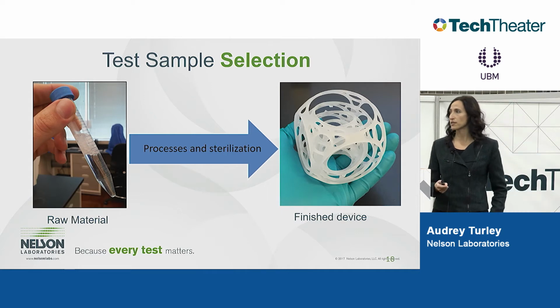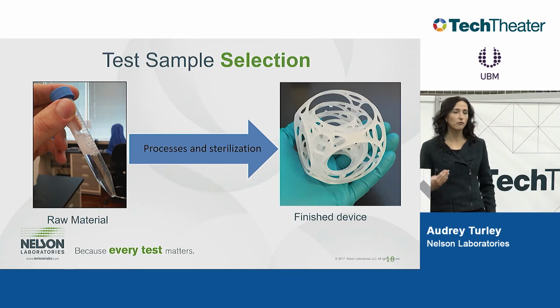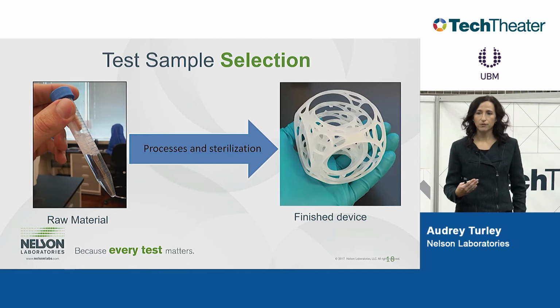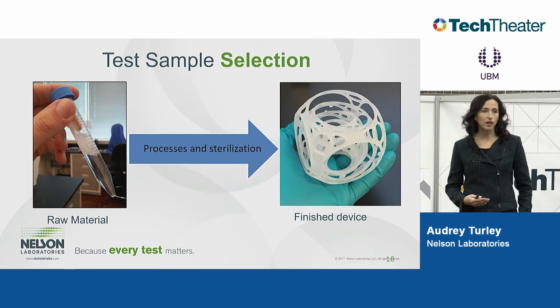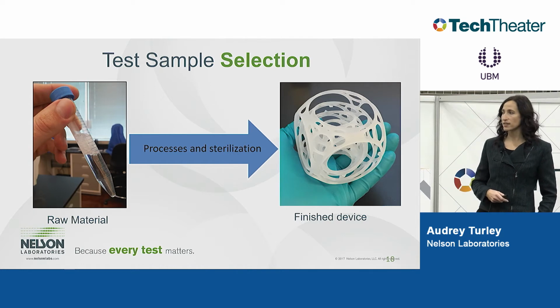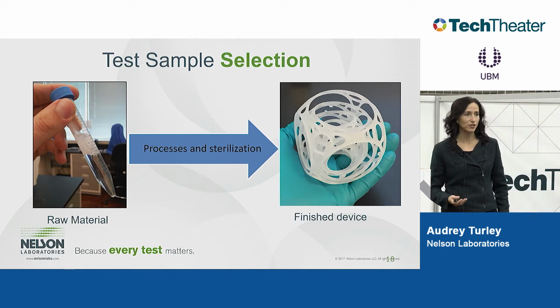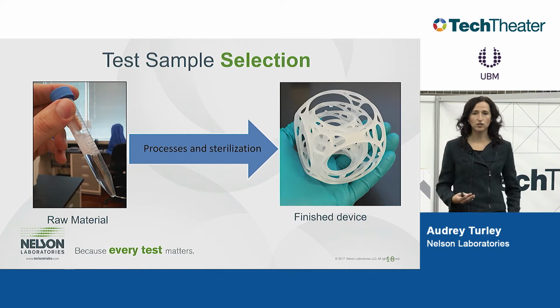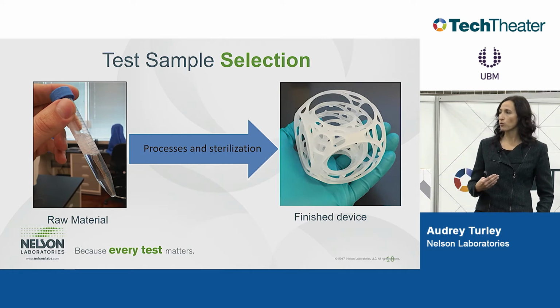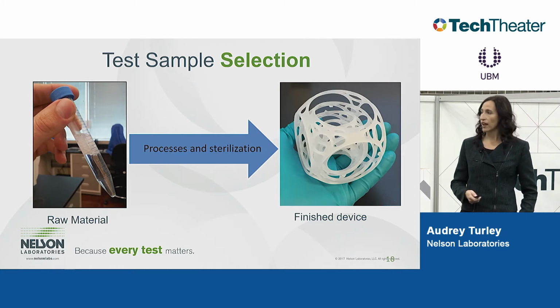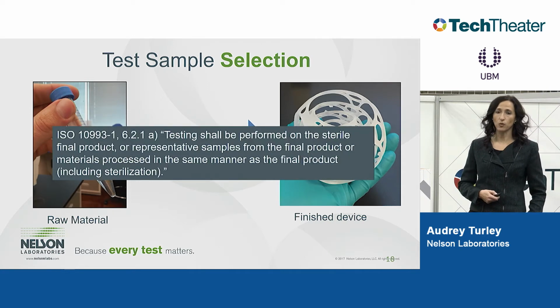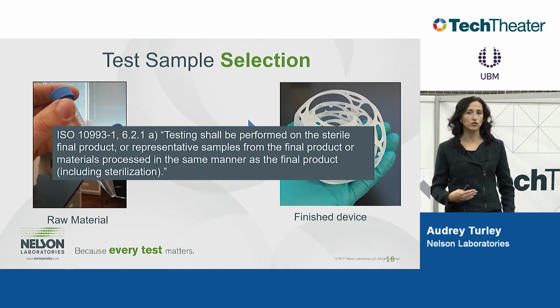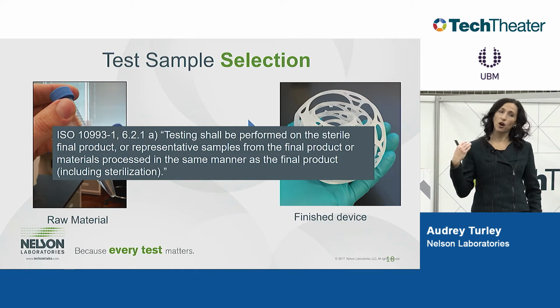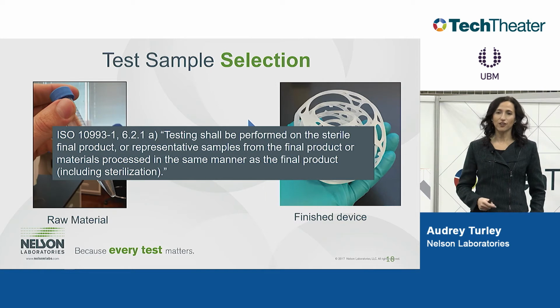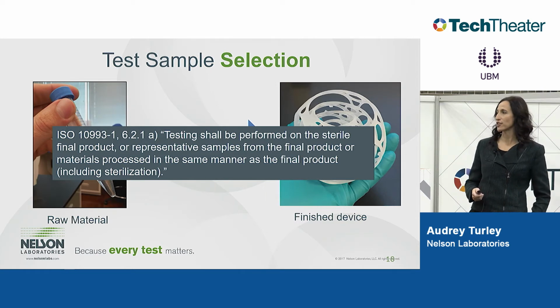Before we talk about the specific tests, I always like to have this caveat up front: even if you start with a biocompatible raw material, it is important that we are analyzing this finished device, because processes and sterilization can impact it. Clearly it gets changed, things get added to it, the plastics change—so we want to make sure we're assessing this finished device. It is stated in ISO 10993-1 to use a device in its final finished form, as final as possible. So if you are working things out with engineers, or you are an engineer, you can use this as leverage that you really need this final finished device for your testing.